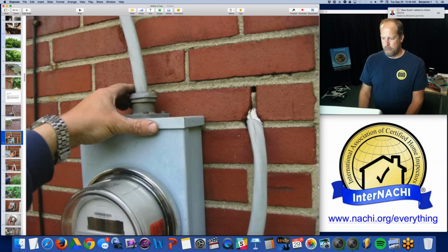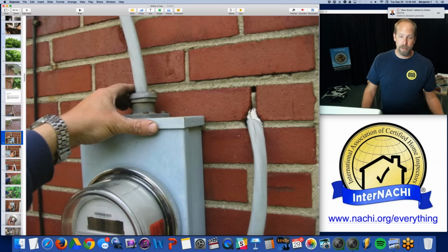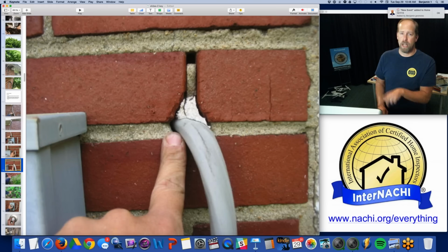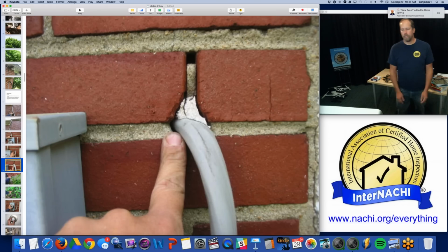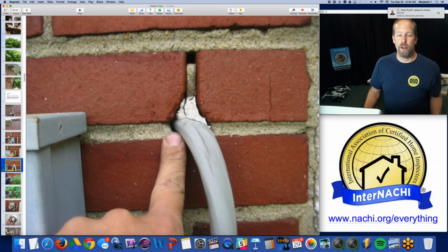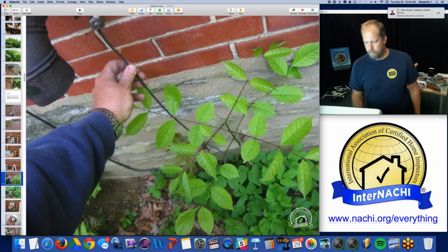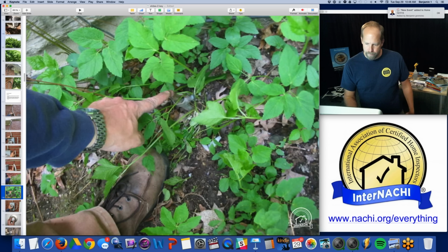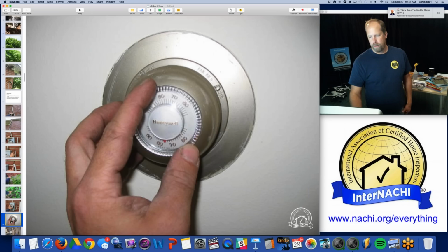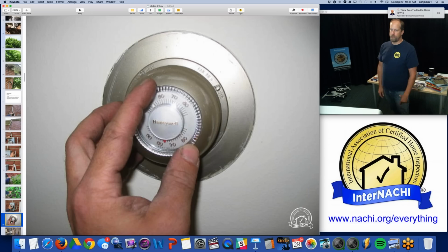We're running a little bit late. I try to pull the meter off of the house. Sometimes they fall into my hand. The condition of the conduit line, the sheath around the line going to the electrical panel, that area there should be sealed up. That's really minor, but I include that photo with my report. There's the grounding wire, grounding rod, acorn.